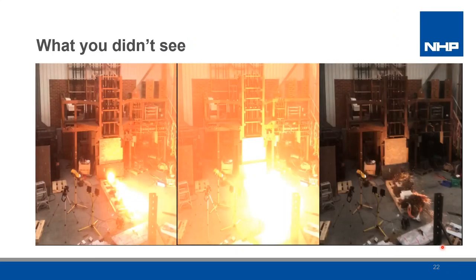But what you didn't see is, as the MCCB trips, arcing gases are vented, plus material is melted and vented also. So you can see with the arcing, both contactor and circuit breaker, and here material is being vented from both devices. Whilst the three-phase bolted short circuit fault is the least common, you have to consider the energy released as the circuit breaker and contactor interrupt the fault, giving off heat and pressure.